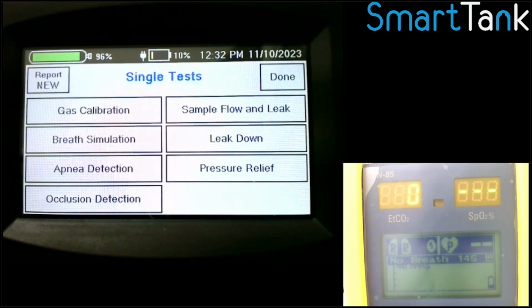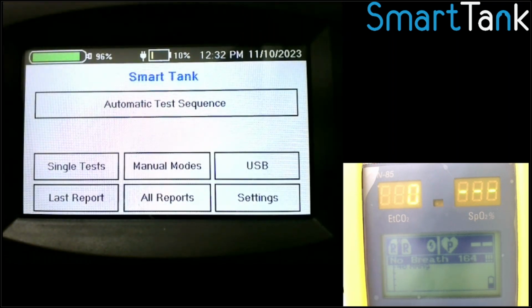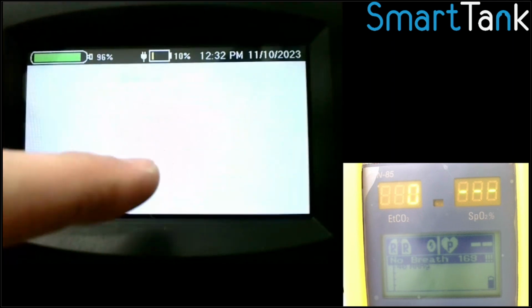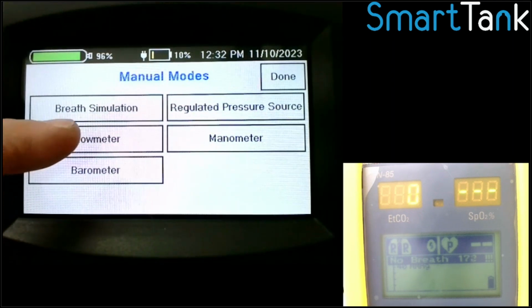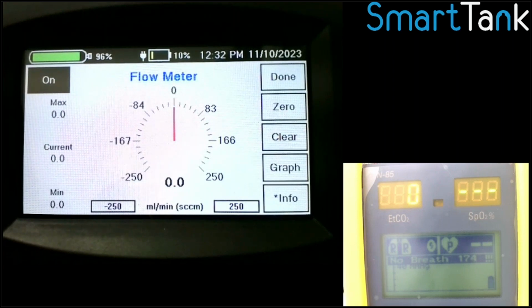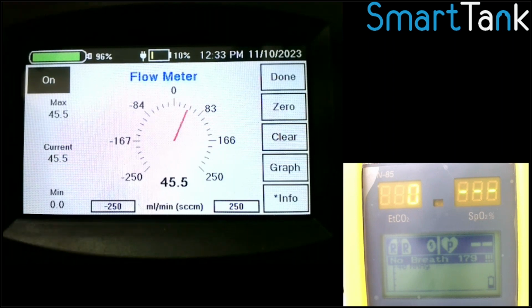So if you ever do non-invasive blood pressure, this pressure relief is the safety test to make sure that it opens safety valves at a certain pressure, so the SmartTank will do that. We have customers who use the SmartTank to do all of their non-invasive blood pressure testing. Since the SmartTank has built into it a barometer, a manometer or pressure gauge, and a flow meter, we make those available also, where you can come in and see what the flow rate is on something.